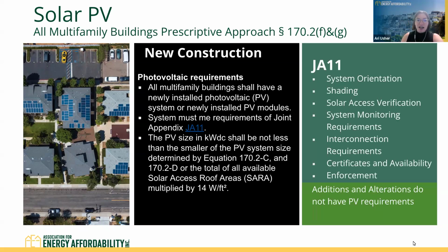All multifamily buildings shall have a newly installed PV system meeting the requirements of Joint Appendix 11. The sizing is determined by the equations in section 170.2, or the total of all available roof area multiplied by 14 watts per square foot. The smaller of those two is your sizing.